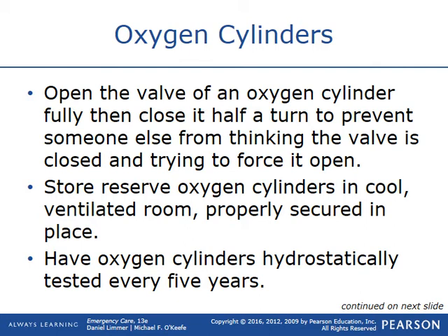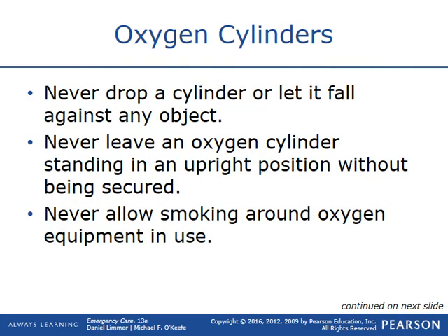Store any reserve oxygen cylinders in a cool, well-ventilated room and make sure that they're properly secured in place. And have the oxygen cylinders hydrostatically tested every 5 years to make sure that they're still safe to operate. Never drop a cylinder or let it fall against any object. Make sure that you never leave an oxygen cylinder standing in an upright position without it being secured. And never allow smoking around oxygen equipment that's in use.